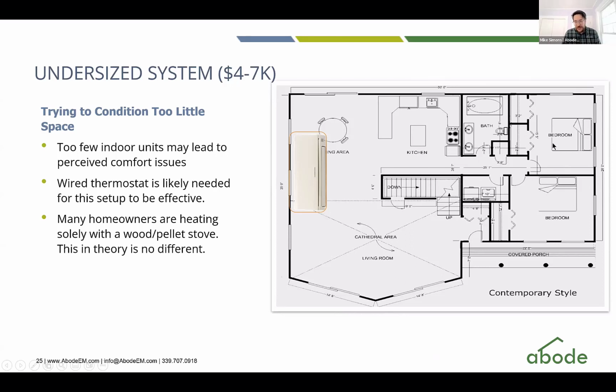And then the further away from the unit that you get, it's going to become colder and maybe it could even become uncomfortable. But this is a perfectly fine approach if you want to have, say, the lowest install cost and you're okay with temperature deltas throughout the home, which I think in, say, a region like Maine, where a lot of people are very accustomed to wood heat, is not that big of an issue. But say in Massachusetts, where more people, I guess, are familiar with or expecting, say, central heating systems and central distribution systems, and every room being probably within like a 1 to 2 degree delta of the next room over, this may be a little bit risky in terms of comfort.